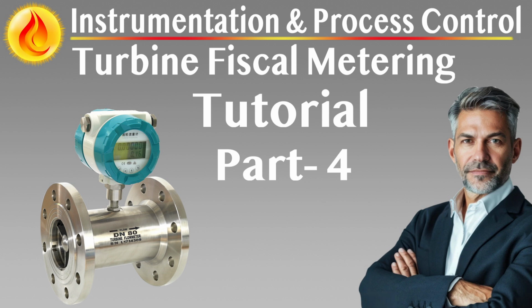Mechanical components, such as guide bars and tees, must be designed to support the smooth transit of the prover sphere without deformation, misalignment, or abrasion. These elements must be precisely machined to avoid interference with the detector switches and to maintain uniform contact between the sphere and the prover bore. Together, these design features ensure that the meter prover delivers repeatable, traceable calibration of turbine meters, forming a critical foundation for legal metrology compliance, quality assurance, and high-integrity custody transfer.